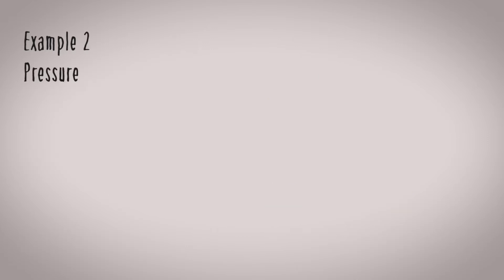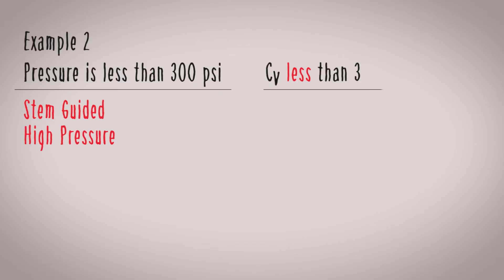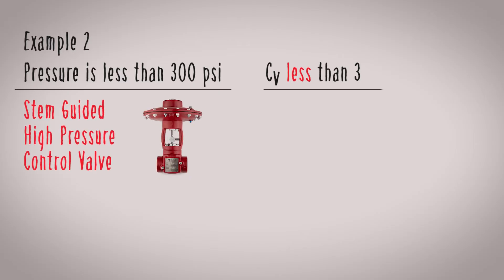In example 2, your pressure is still less than 300 psi, but your required CV is less than 3. In this example, you should use a stem-guided high pressure control valve because it can meet your small CV requirements.